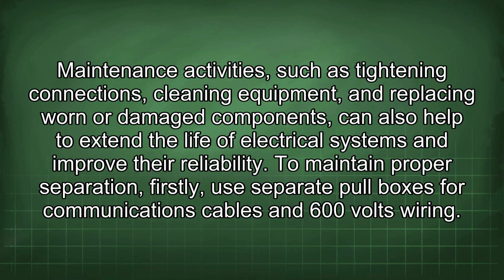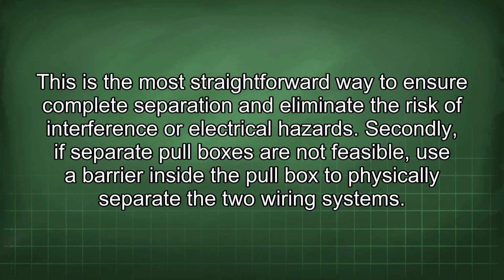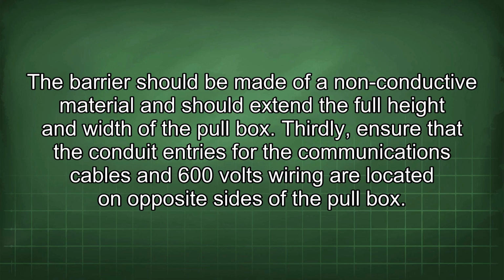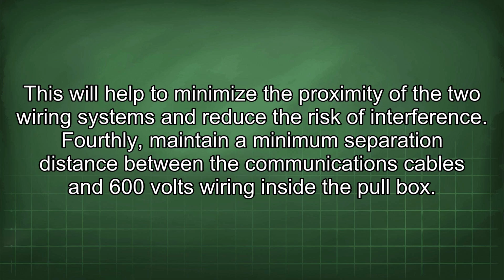To maintain proper separation, firstly, use separate pull boxes for communications cables and 600 volts wiring. This is the most straightforward way to ensure complete separation and eliminate the risk of interference or electrical hazards. Secondly, if separate pull boxes are not feasible, use a barrier inside the pull box to physically separate the two wiring systems. The barrier should be made of a non-conductive material and should extend the full height and width of the pull box. Thirdly, ensure that the conduit entries for the communications cables and 600 volts wiring are located on opposite sides of the pull box. This will help to minimize the proximity of the two wiring systems and reduce the risk of interference.